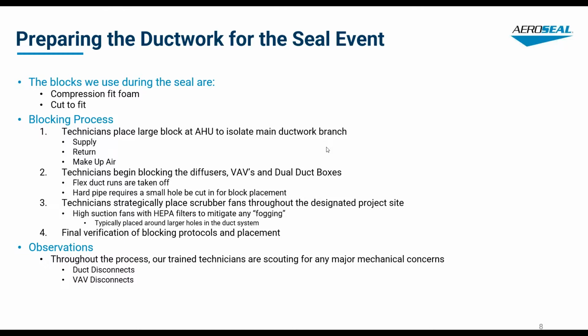Then we have observations. Throughout the process, our trained technicians are scouting for any major mechanical concerns: duct disconnections, VAV disconnections, any mechanical repairs needed. You know, we find a lot of things in these buildings. We'll find times where there used to be a VAV and they tore the VAV out, but there's still an 8-inch or 10-inch round opening in the ductwork, blowing high pressure air straight out of the main trunk line. If we see instances like that on the project, we typically will just go ahead and take care of it. We'll capture the savings. We'll do a pre-seal so that we know how much it's leaking, and then we'll cap it off so that the customer is able to see the difference on the seal certificate.